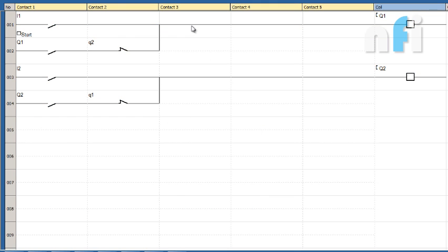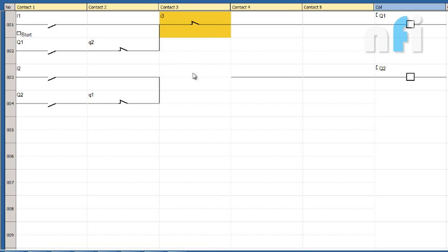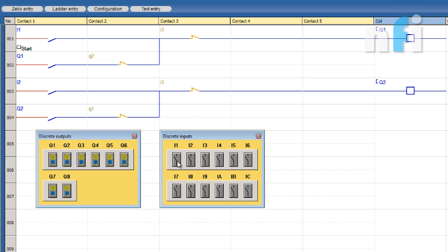For that, you can take I3 NC here as well. We can take multiple contacts of the same inputs. That's the flexibility we have here. So now this will work as interlock as previously, and this I3 is going to turn off the interlocks. That's how it works. Okay, so this was an interlock circuit which we can make using simple NO and NC contacts. I hope this concept is clear up to here.